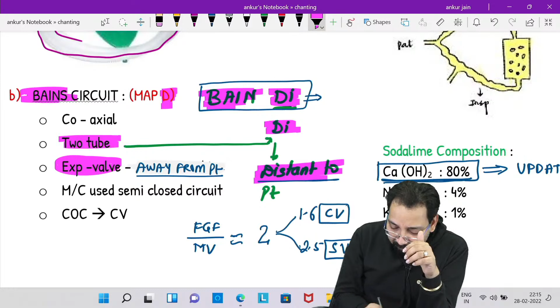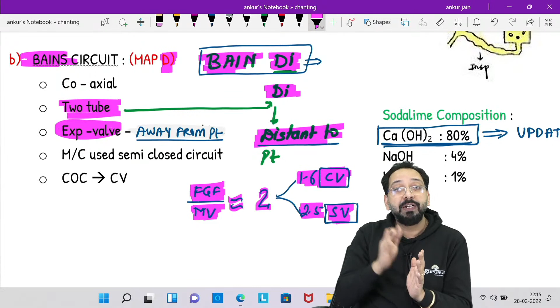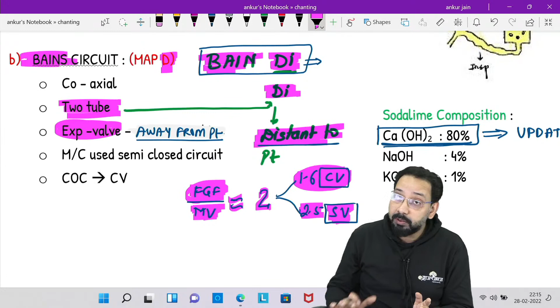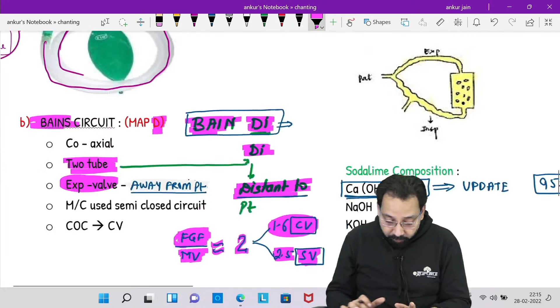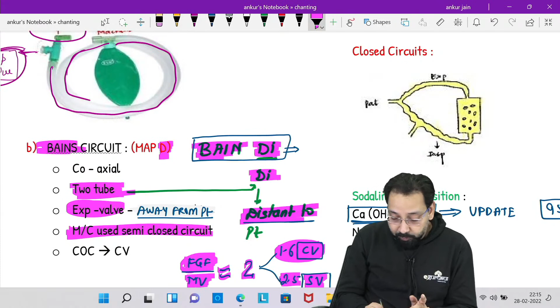And the ratio is near about 2. How to remember? In controlled ventilation, the ratio is 1.6, less than 2. If spontaneous ventilation, more than 2.5. So if fresh gas flow is 1.6 in controlled ventilation, we will prefer it for controlled ventilation. Clear? It can be used in spontaneous ventilation, but the flow of fresh gas would be high. Clear? So this is most common, two tubes, DI, distant from the patient.